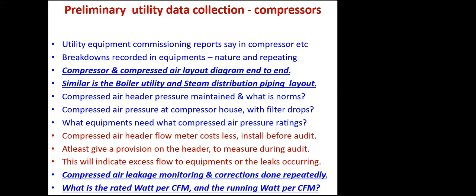But it is always better to install it before the audit. Once the compressor is installed, you need to support it with a compressed air flow meter also. Then only we know the generation efficiency. In compressors, we always talk about watt per CFM. In many industries, they say their watt per CFM is almost 220 to 250 watts per CFM of compressor, whereas the latest generation compressors are operating at 150 to 160 watts per CFM. This is what we want now. Next, please.